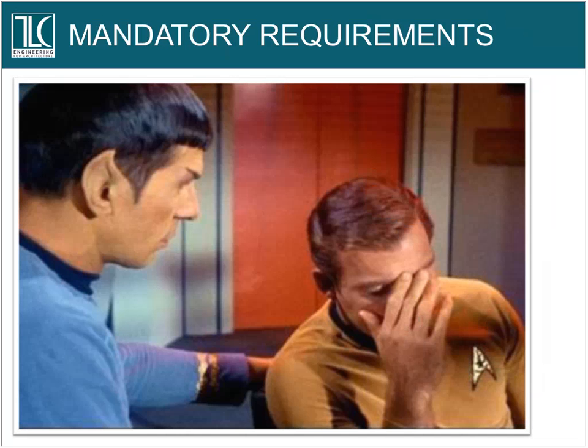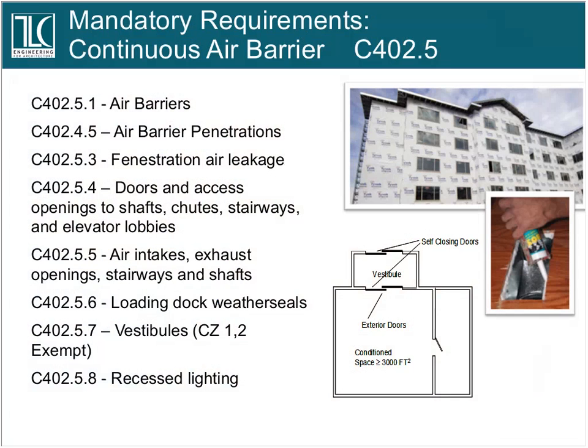Now there are some mandatory requirements, things that you have to do no matter what, even if you do a performance model. And one of the most significant of those is a requirement for continuous air barrier. In earlier versions of the code for the southern climate zones, this was not a mandatory requirement. It is now. And this is a really hard thing to add once the building is up and the code guy walks out and says, show me your air barrier.